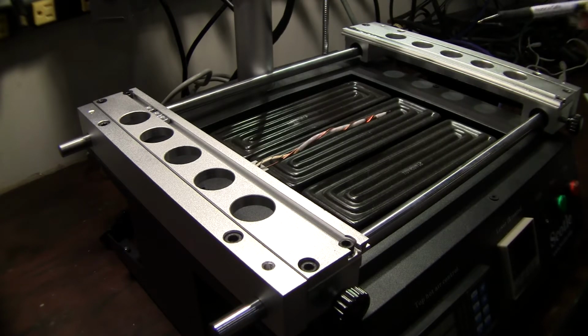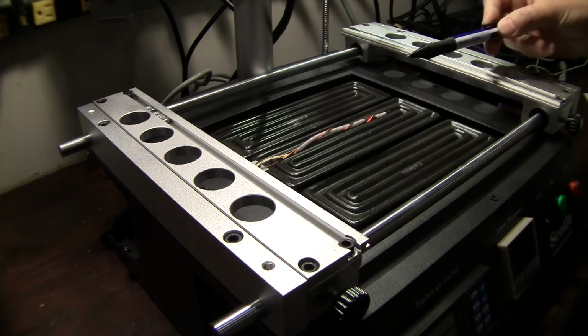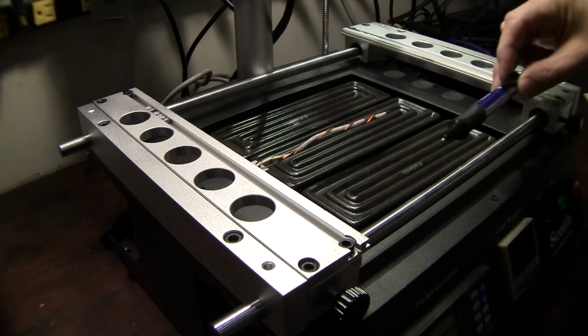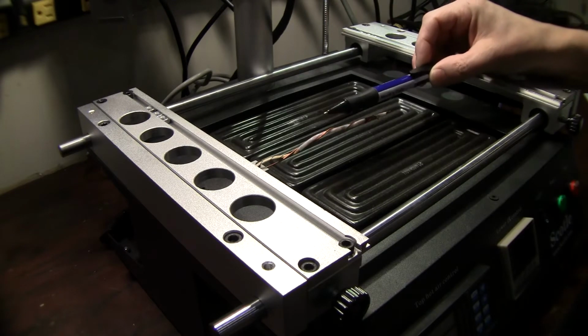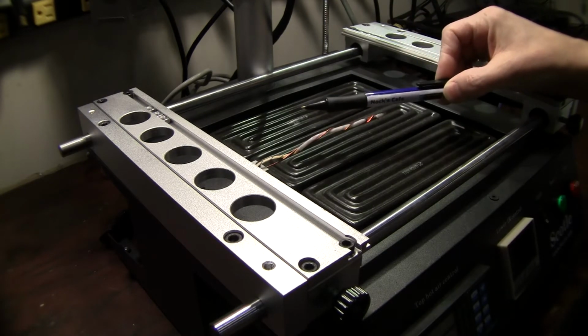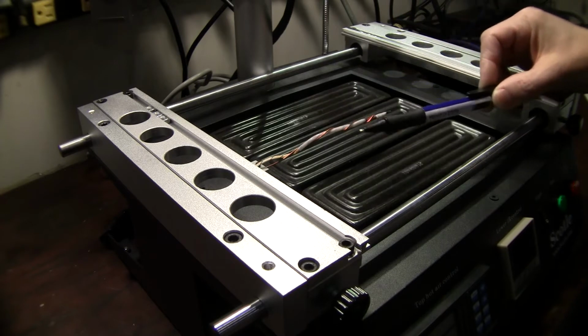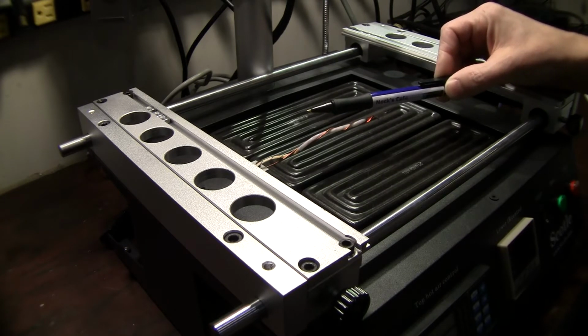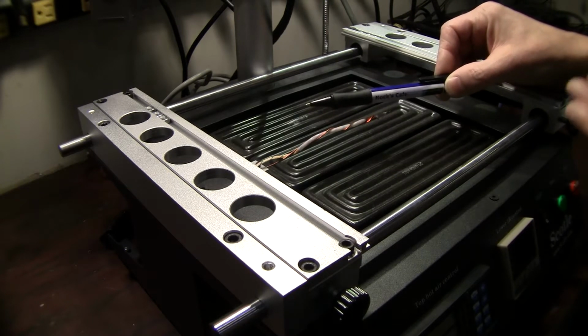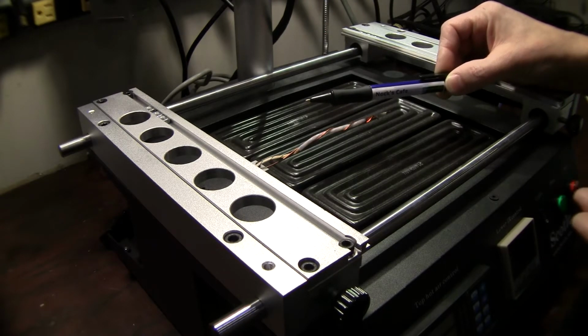And it really doesn't matter what lower heater type you have, because again, we're basing this on a flatline model. And our flatline model is like this. What it accounts for is if your board is on your rack and your probe is within 1/4 inch under the board, meaning the board's plane is here and your probe is just there, about 1/4 inch below. It's not able to contact the board, but yet it's not far away from the board. It's in very close proximity.